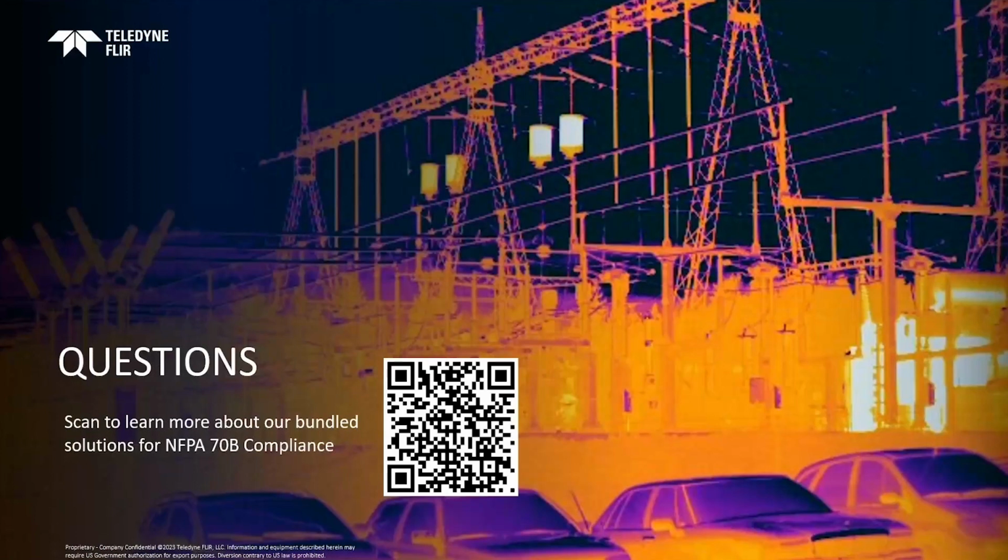building. We have the procedures and the recommended test methods in NFPA 70B. Once we begin a list, it's beginning to build a schedule. And then the most important thing is how do you gather, keep, and record all that data? I know I'm making a plug here, but our Thermal Studio plus our Route Creator software permits us to not only keep a list of the equipment and what needs to be checked, but also gives us the ability to create a place of storage for the data that we collect, images and other data with our other meters. And now it becomes historical.